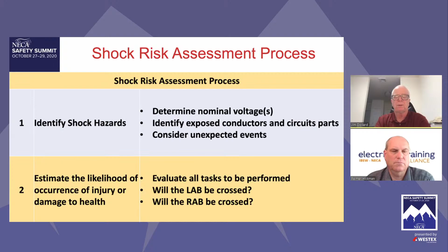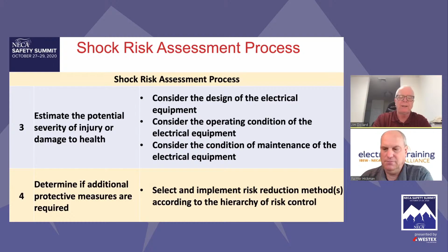Let's take a look at every task that we're going to perform. Then estimate the potential severity, which would include the design of the equipment, the operating condition of the equipment, and the condition of maintenance. And Jim, step 4 there is really the essence of this. You've identified a shock hazard. Now we're going to say, do we need additional protective measures? What most people would do is say, I'm getting shock protection, I'm doing the work. But this is where we have to say time out, go through those 6 steps, try to eliminate, try to substitute, and then if we get the PPE, we get the PPE. Absolutely. We're down to just over 2 minutes, and Jim, that's the additional protective measures, and we'll be able to get through these couple, and then that's the end.